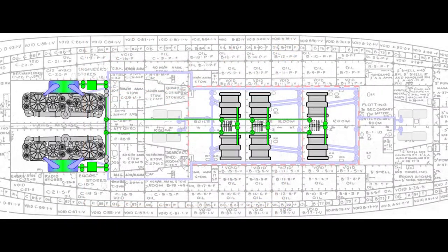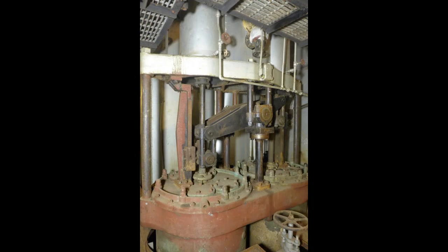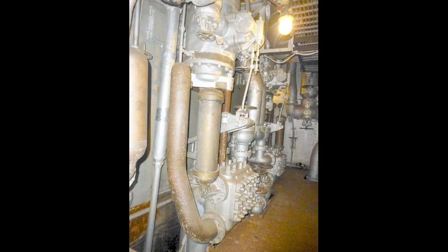Let's move on to fresh water. The boilers require huge amounts of it to make steam. The basic feed water system starts back at the engine rooms where large condensers convert waste steam back into water. From there, air pumps, which are actually vacuum pumps, provide suction that removes dissolved air from the water, improves performance on the engine's low-pressure cylinders, and pushes water into the hot well, which is also called the feed water reserve tank. Feed water is then pumped at a pressure of 400 psi back into the boilers.